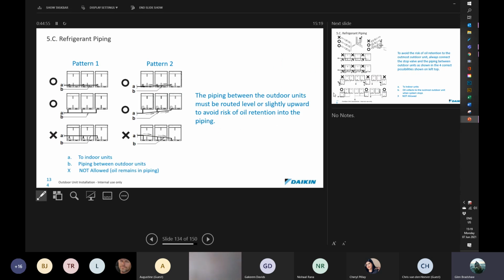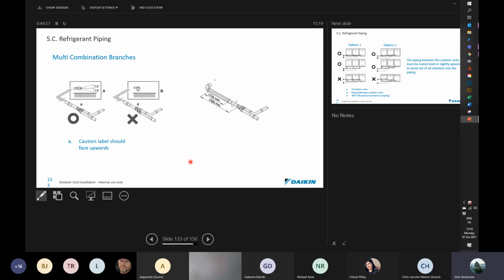All right, the reason, rather than just telling you, is that you must understand that the oil traveling along this pipe is going to be traveling generally near the bottom because of gravity, and more oil is going to flow along the bottom than along the top. That means you're going to get uneven oil distribution back to your condensers, and eventually one condenser set will have too much oil and the other condenser set in the front of the piping will have too little. Both of those circumstances will cause damage to compressors, too much and too little oil.